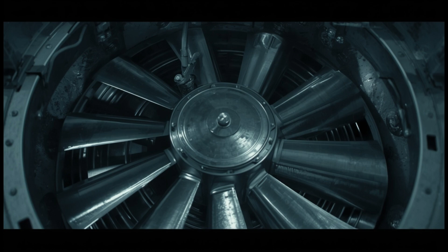This blending serves a purpose that runs deeper than simple convenience. By combining a portion of already conditioned return air with fresh outdoor air, the system spares itself the far greater cost of conditioning the entire volume of air from outdoor conditions alone. Bringing in 100% outdoor air, particularly on a very cold or very hot night, would demand an enormous amount of additional heating or cooling capacity, consuming far more energy than the building actually requires to remain comfortable and properly ventilated. By blending instead, the system provides enough fresh air to maintain healthy indoor air quality, while relying on the return air to carry forward a meaningful share of the conditioning already achieved. It is, in its own quiet way, an act of conservation built directly into the architecture of the machine.